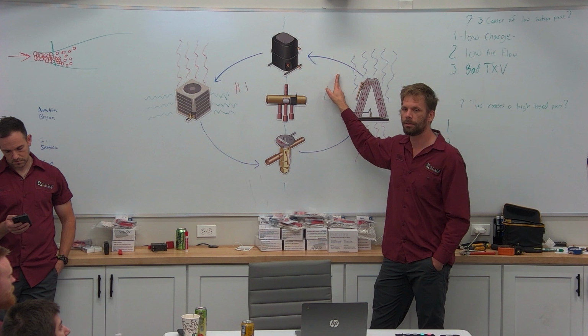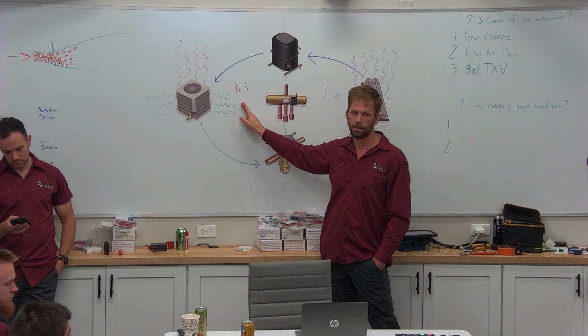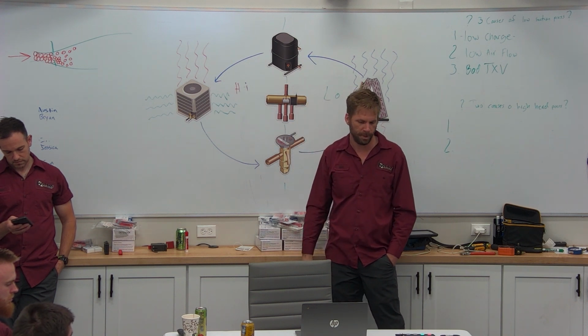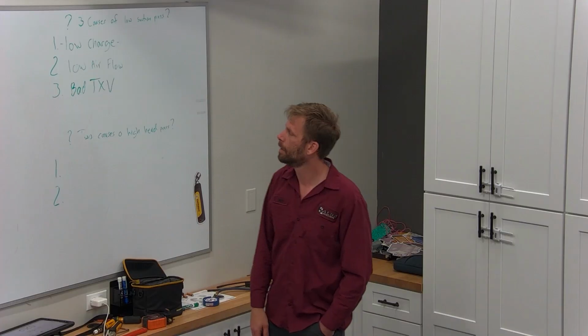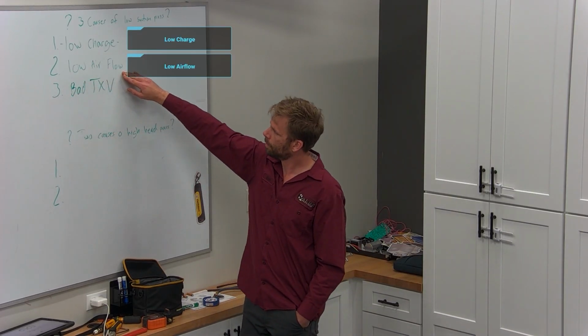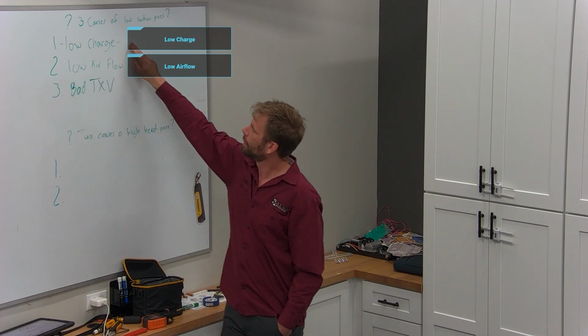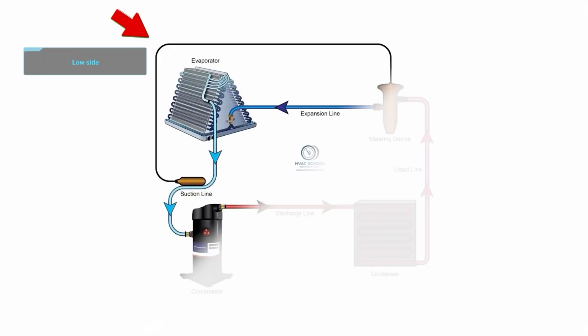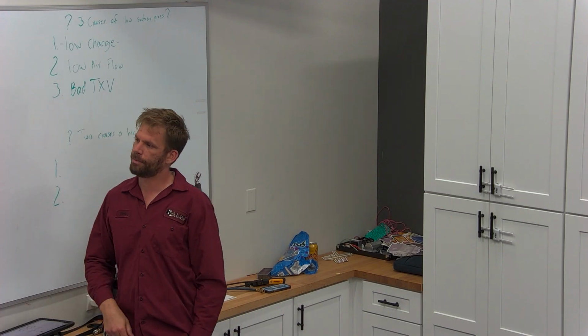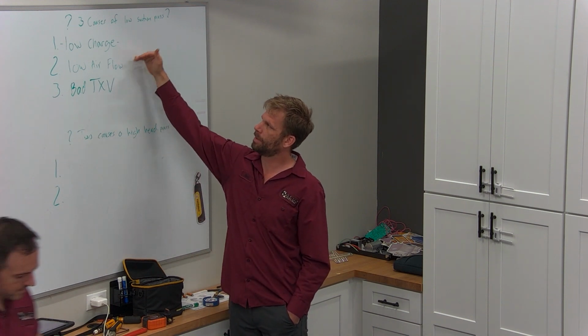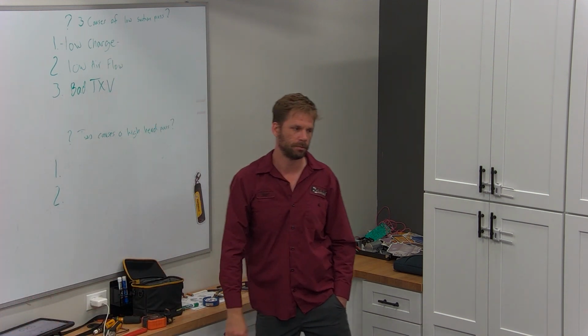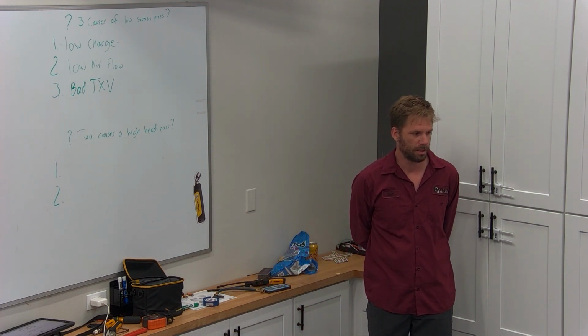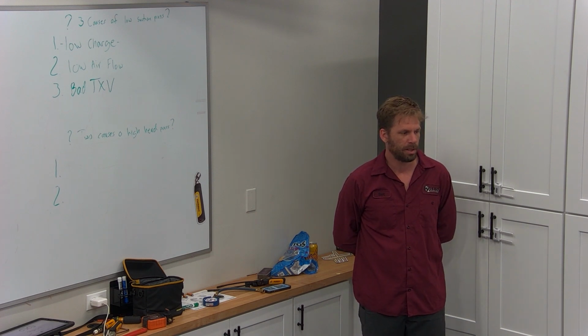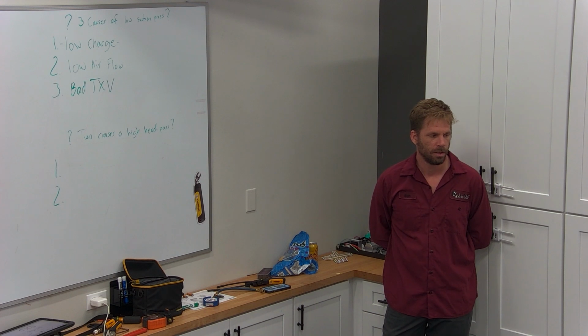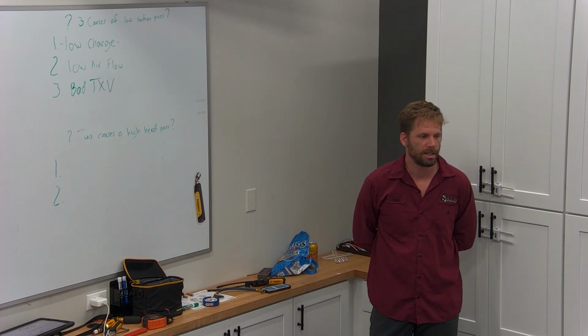If your low side is giving you the low refrigerant signal, but your high side is great, you have a restriction. All right, now airflow. Low airflow. What is going to be the difference between my low airflow and my low charge? They share a very distinctive difference on the low side. Let's say we don't have anything to hook up to the high right now, only a low, and we have to find the difference between airflow and these two. It is how quick your boiling changes. But we can't ask a system how quick its boiling changes. We have to do a test that tells us. What is that test called?